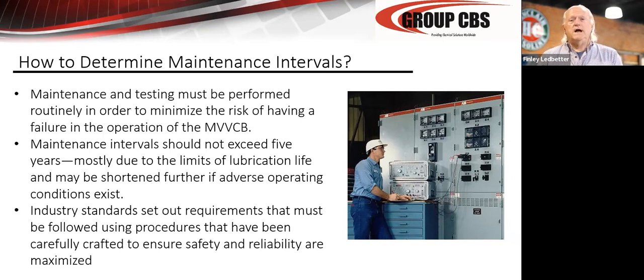Now, when you do your semi-annual or every 5-year or whatever maintenance, you need to do the spares as well. So don't forget that. Don't forget the spares. And I would cycle them through use. At every maintenance interval, I would move a spare into operation, and I would take the other breaker out and put it into spare. And I would do this in my less critical circuits.